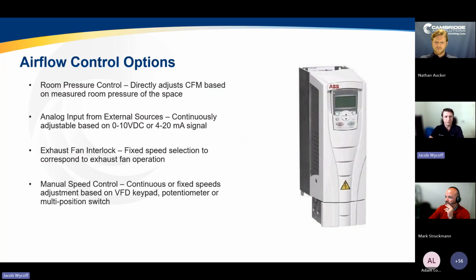The second thing that you want to be thinking about early is how are you going to control the airflow? So most of these manufacturing type applications are going to call for variable airflow needs of some sort. There's a few different ways to go about this that we see commonly. So number one, room pressure control. You have something in the space that's directly measuring the room pressure of the space, and the unit's going to vary the CFM depending on that measured room pressure to attempt to control to a slight positive pressurization in most cases.